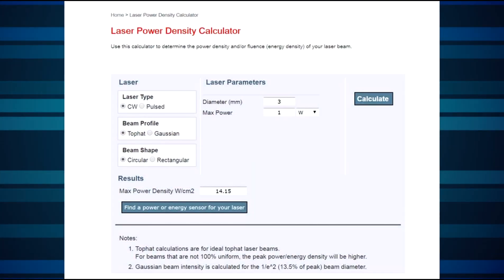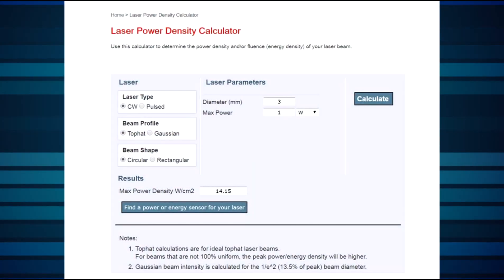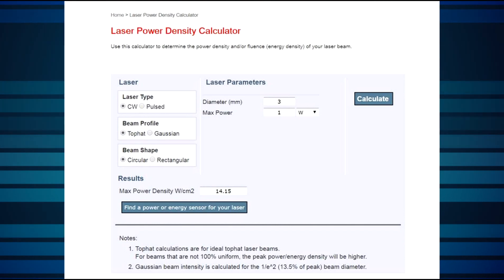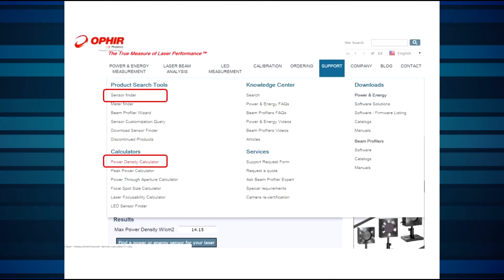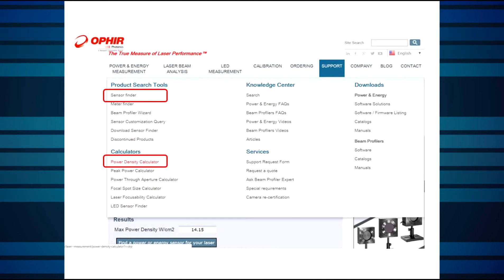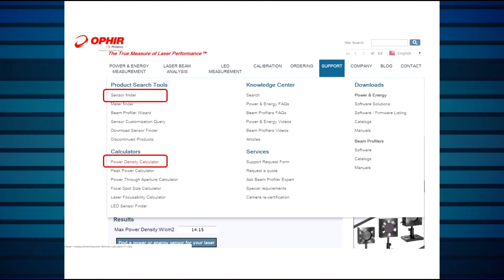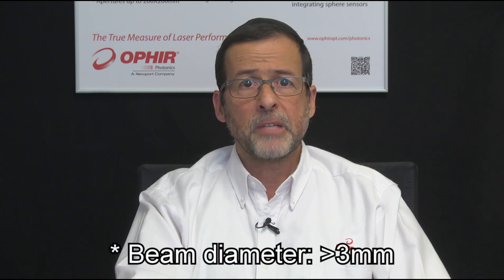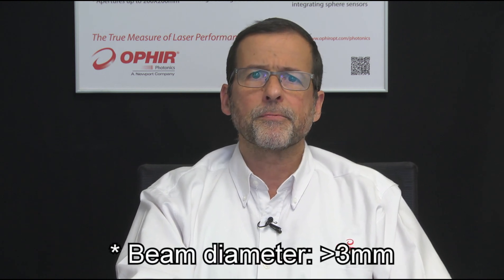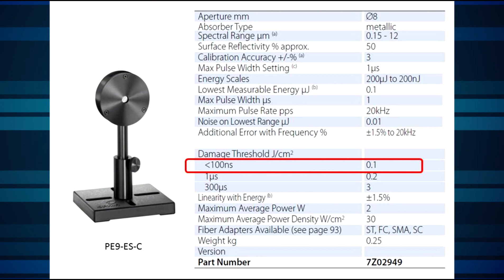With 1 watt of average power, that power density limit is reached with a beam diameter of 3 millimeters. You can check this easily with the sensor finder or the power density calculator tool. So the worst case for average power imposes a requirement for a beam diameter of at least 3 millimeters. Now we'll consider energy and energy density.